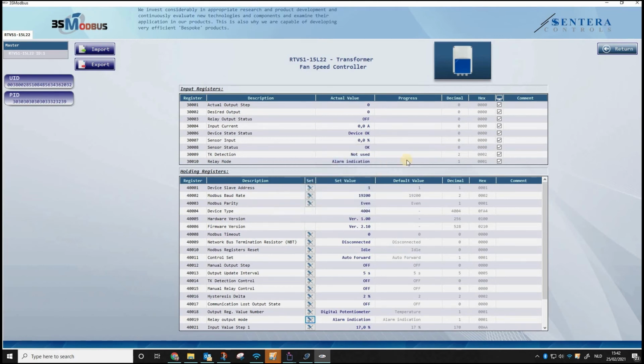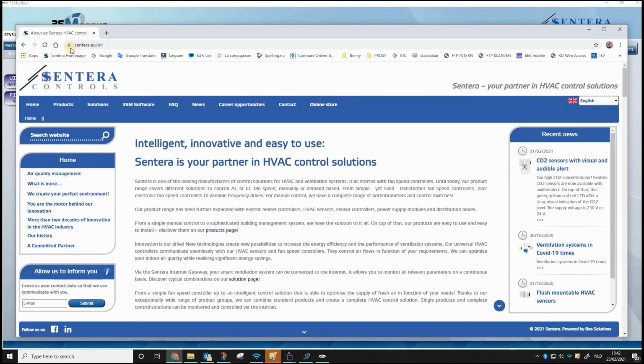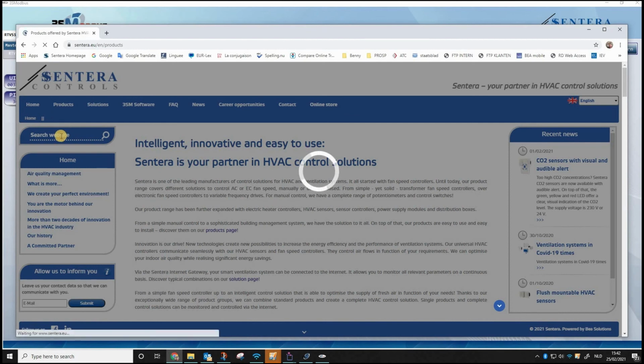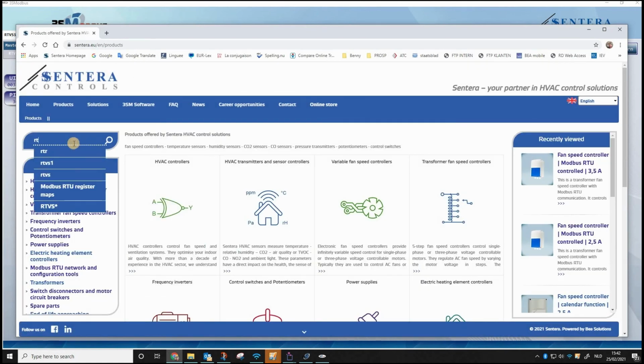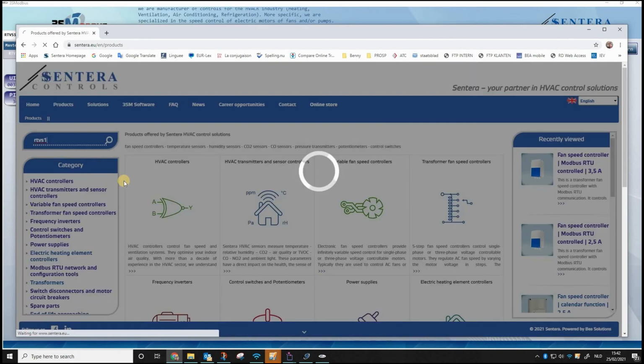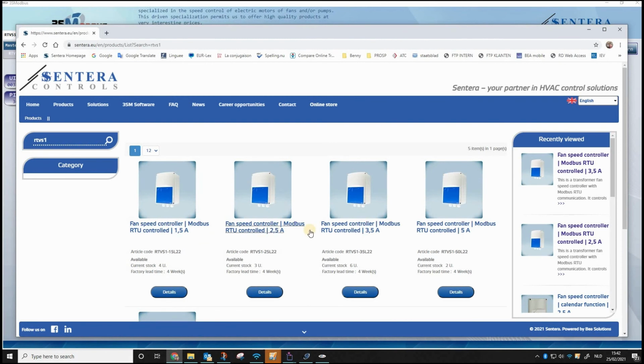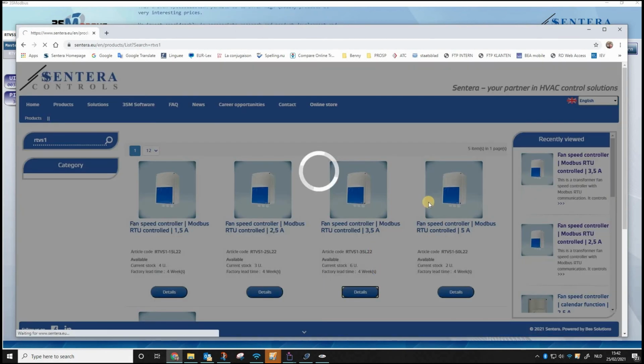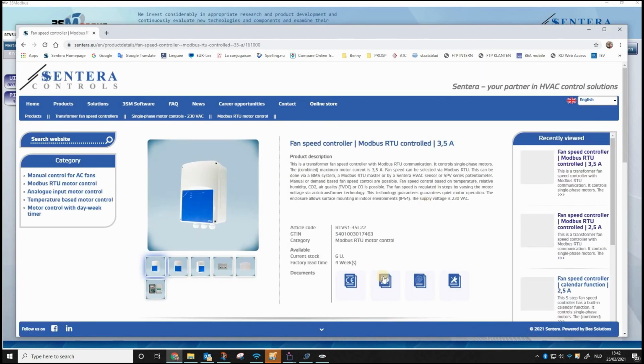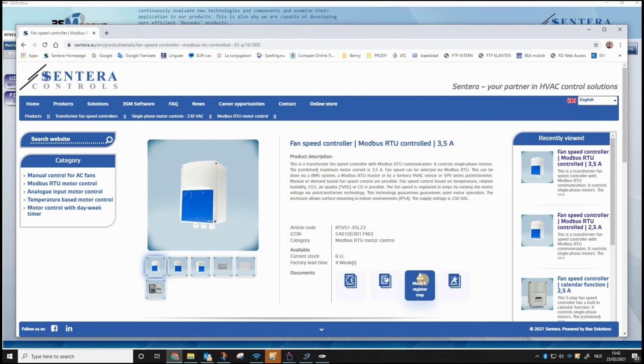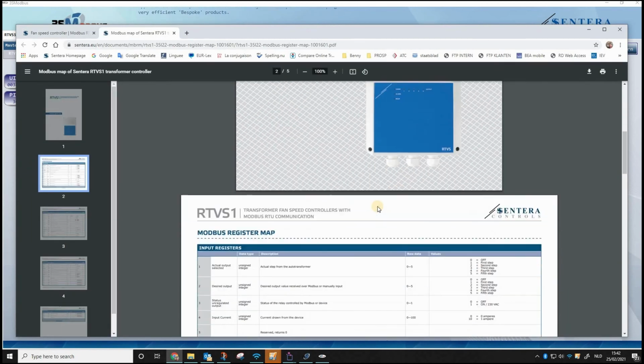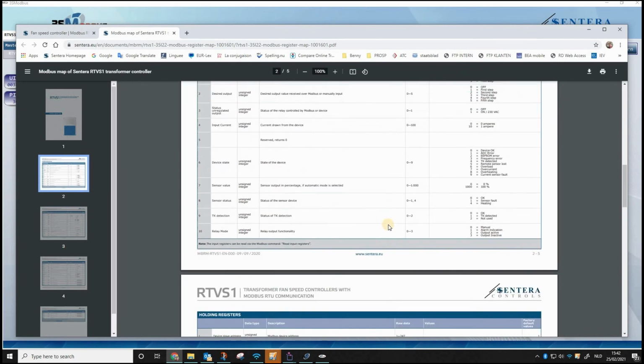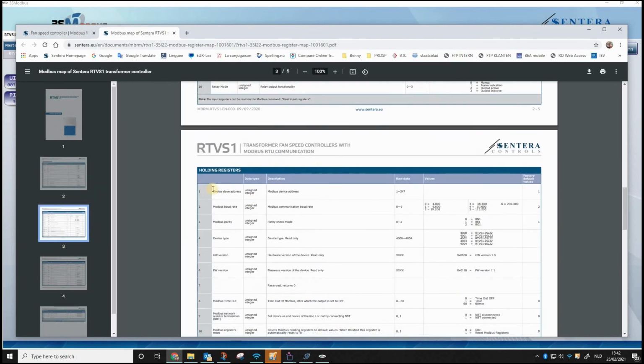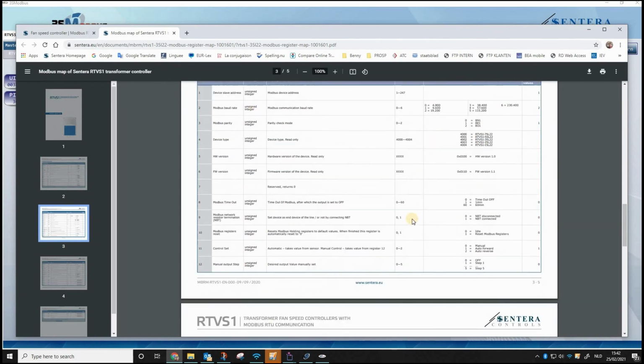We will take a look at the different alarms that can occur as well as the meaning of all those other Modbus registers in the Modbus register map. The Modbus register map for each Sentera Modbus product can be found on the Sentera website. You choose products, enter the name of the device here, then you just choose a device. The amperage does not matter for these Modbus register maps. And in addition to the datasheet and the mounting instructions, you'll find the Modbus register map, where you can get an explanation of all input registers with all possible statuses and output values, and of all holding registers and how to set them.